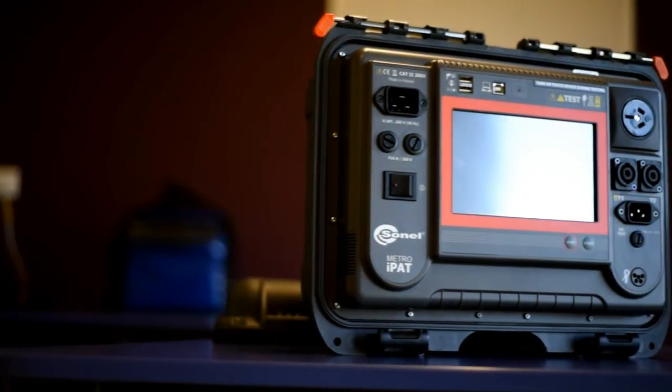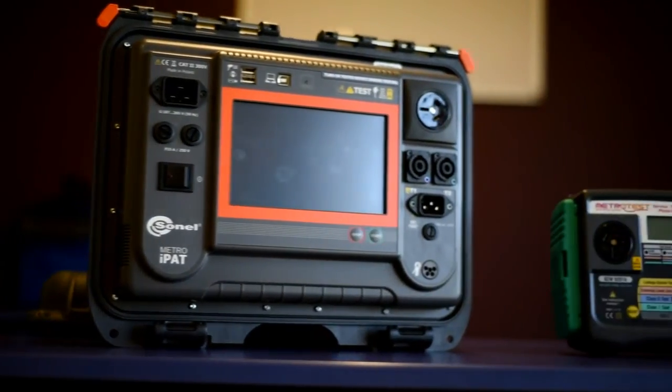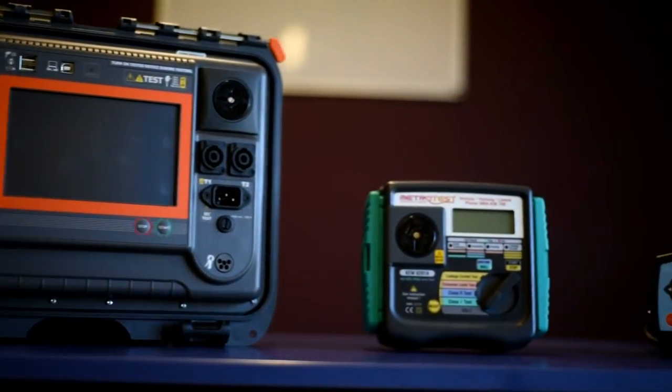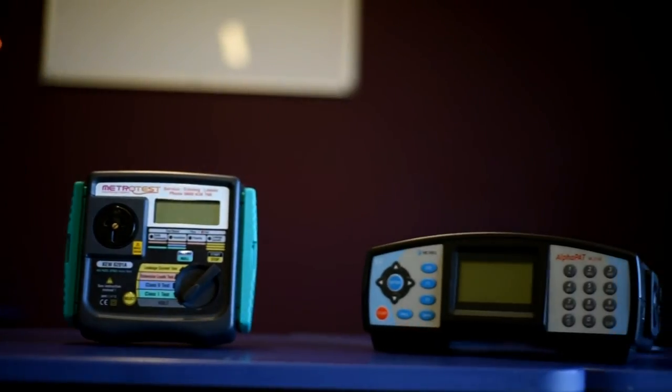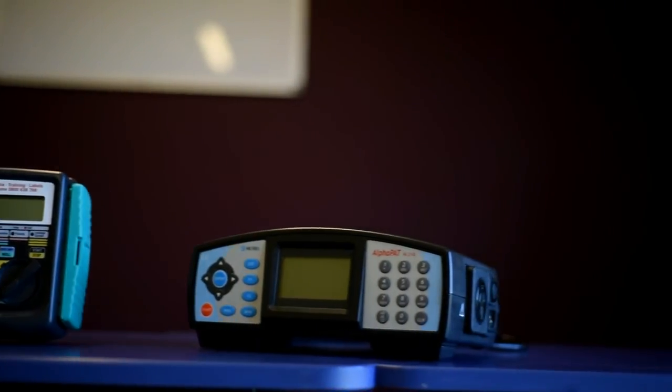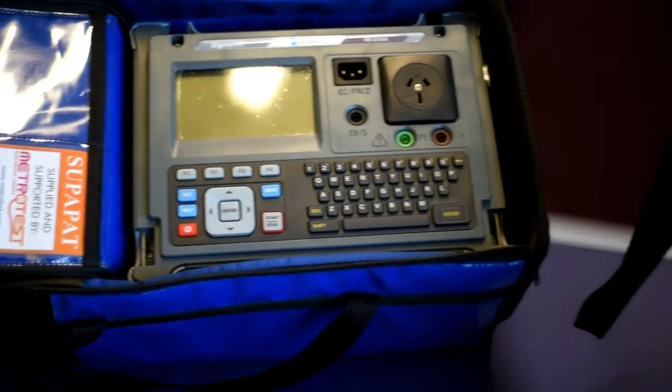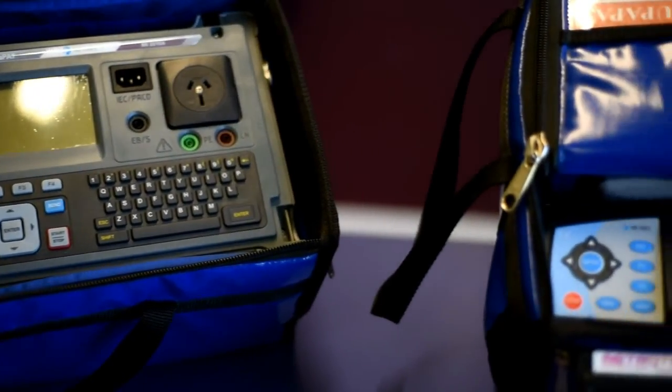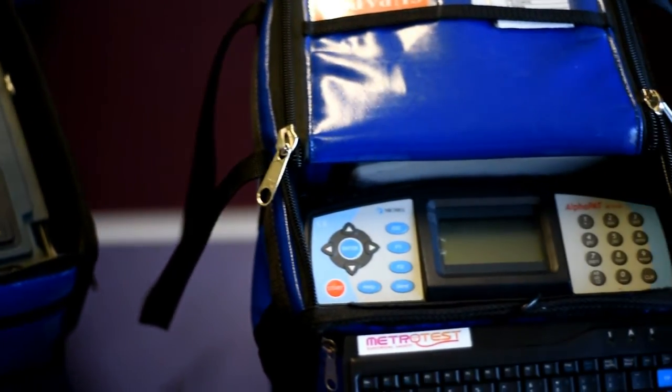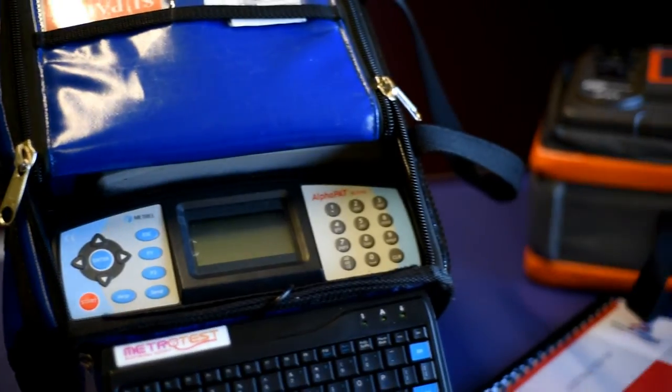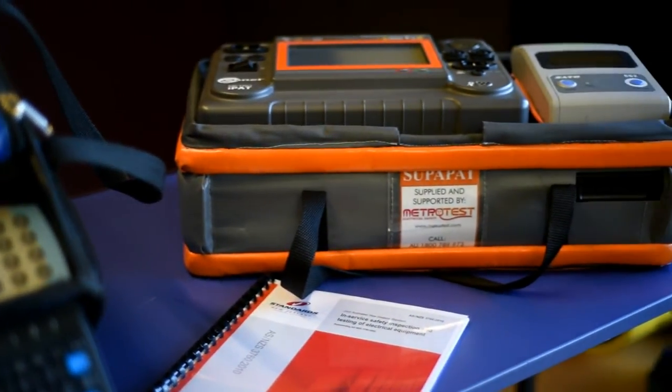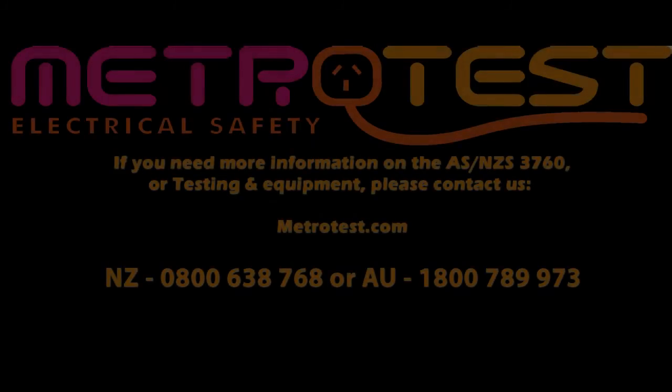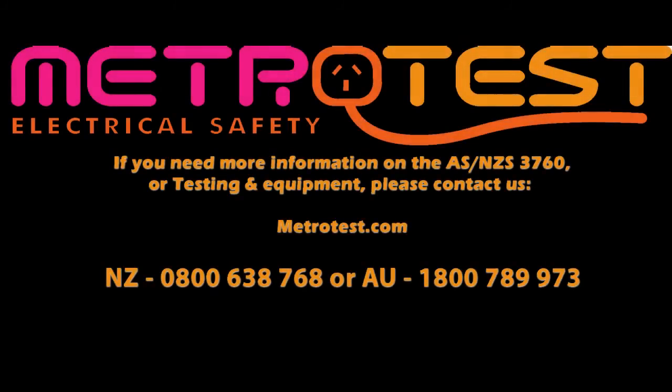There is a wide range of test equipment out there. And while inexpensive units are capable of a 200mA IT test, only some are capable of executing both a hard and a soft test. If the unit you're looking at buying has got a 200mA, a 10A and a 25A under earth on its spec sheet, it's capable of performing a proper earthbond check for safety as well as compliance on all types of equipment.